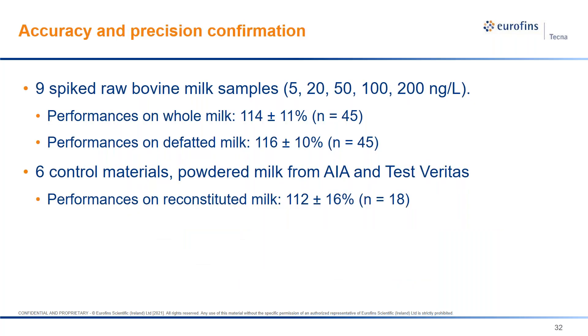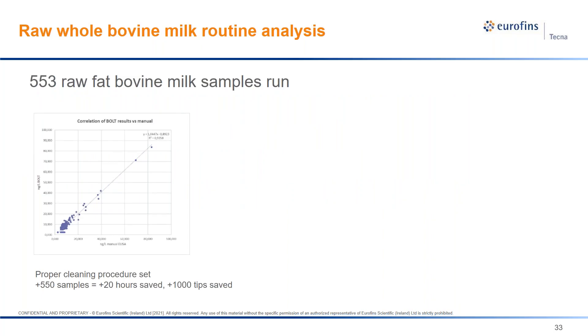I then went for accuracy and precision verification both on spiked materials and reference materials. Fresh milk was used as well, with natural content of fat and other components, as both are a valid procedure in the kit insert. Most importantly, I worked with an external laboratory to stress the machine with routine samples. With a robot or a new machine, a one-shot verification could lead to false results that could deviate in routine as the real matrix sticks to robot components and tubes get dirty. We analyzed around 600 samples in parallel with the robot and manually, getting a very high correlation in terms of accuracy and no drift related to robot aging.